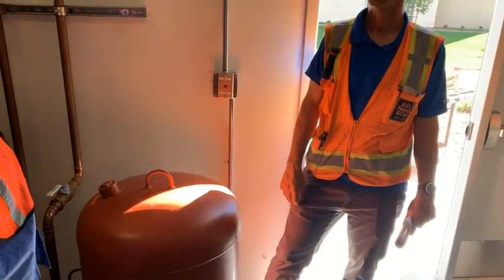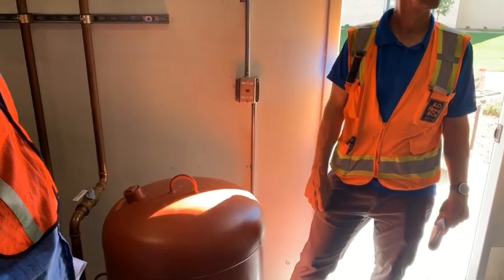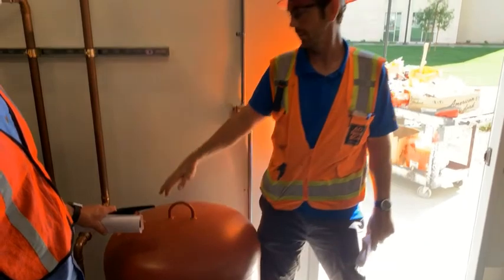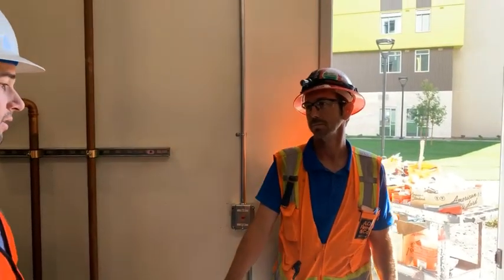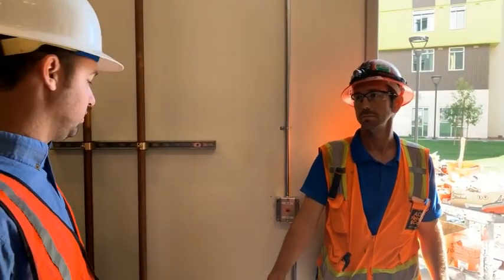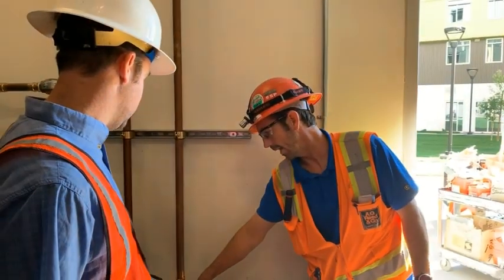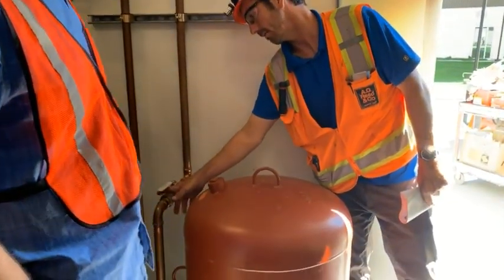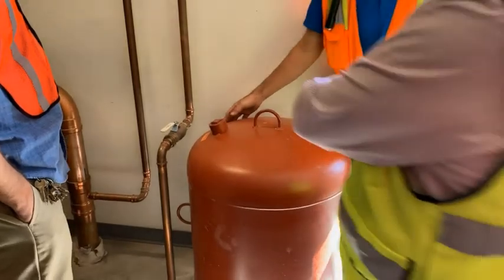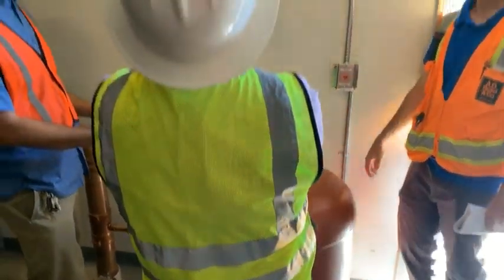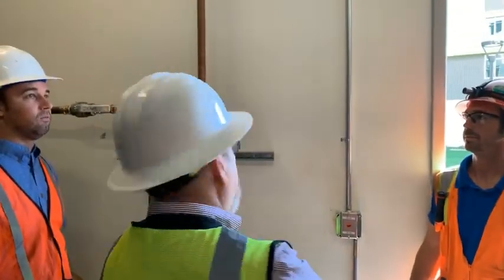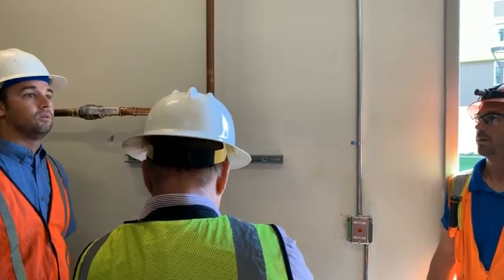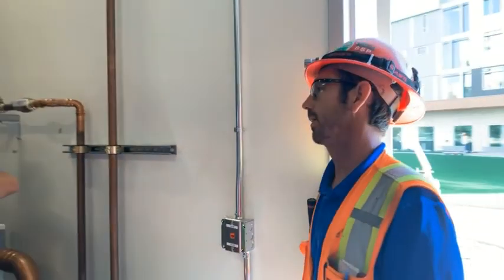Are you talking about a valve? If we had to recharge this, we would have to drain this down. To drain this down, you would shut this valve, get a bucket and a rag, and disconnect this. You tie the rag to the union and it'll drip into a 5-gallon bucket. We don't hardly ever touch these anyways. It's kind of a non-issue. But you do want to check it at least once a year or 6 months.